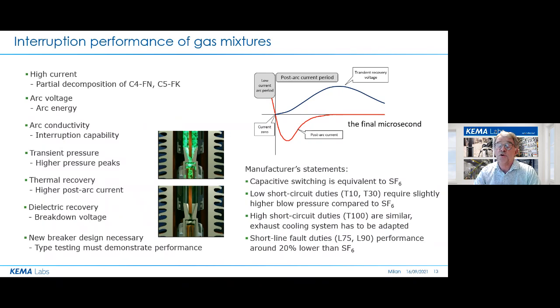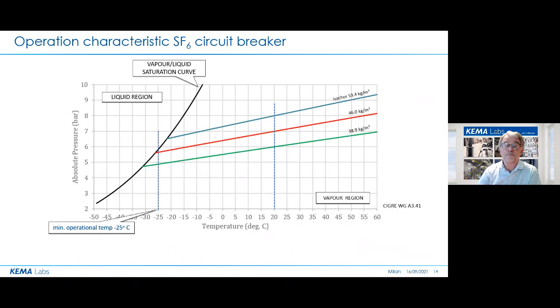The low short circuit duties, which in standardization terms are termed T10, T30, T60, require a slightly higher blow pressure compared to SF6. For the high short circuit duty, T100, the full short circuit current, they seem to perform in a similar way, but the exhaust cooling system has to be adapted in a new design. Well, regarding the most critical test duty of all, the short line fault, the L75, L90, performance seems to be around 20% lower than SF6. So again, new designs need to be adapted for that.